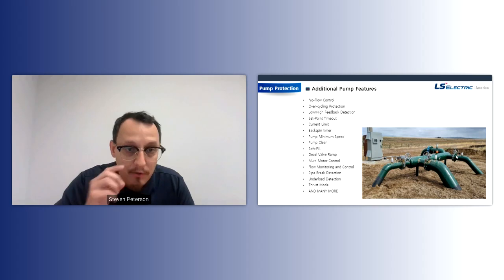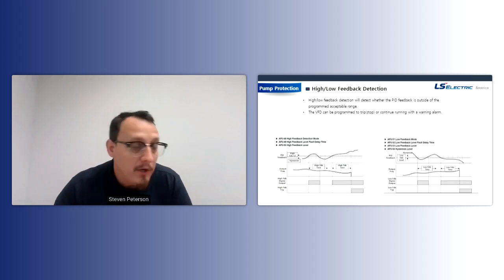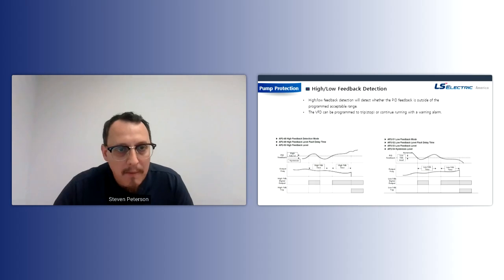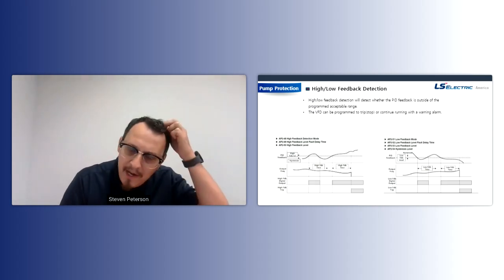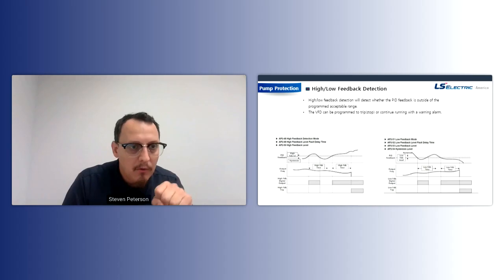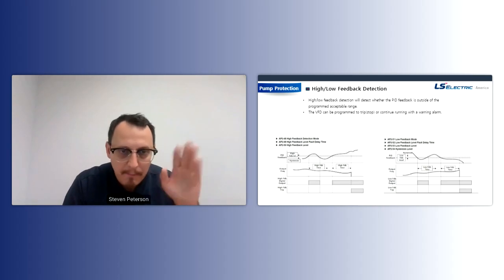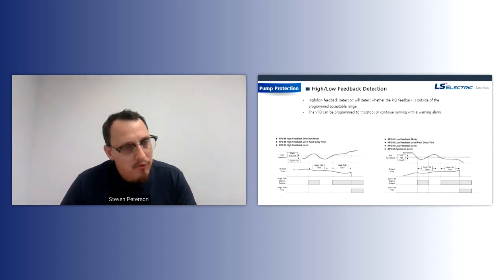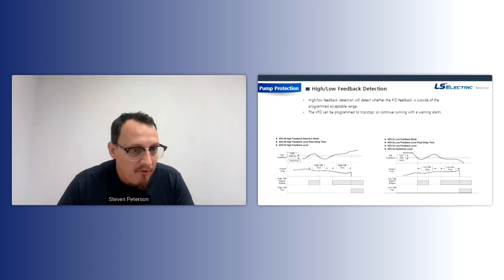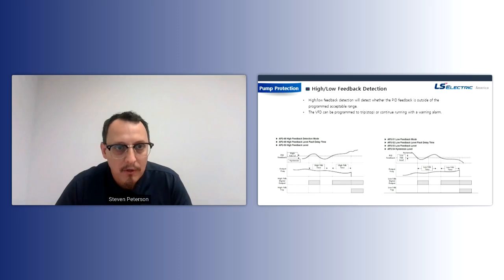What I did do is pick out a few that we use on a day-to-day basis. These are all protection functions. High and low feedback detection is a very important one, because these apply to both hand and auto. I didn't talk about hand so much, but hand is a basic keypad run command. So you hit the hand button, you ramp it up to 60 hertz, which is great. But the problem is if you're running a pressure control loop, hand doesn't really care about your pressure unless you set up a high feedback detection level.